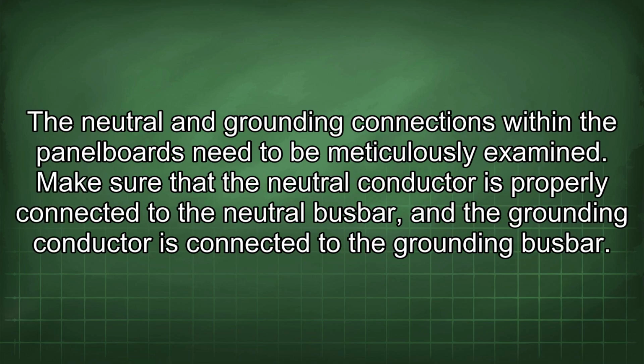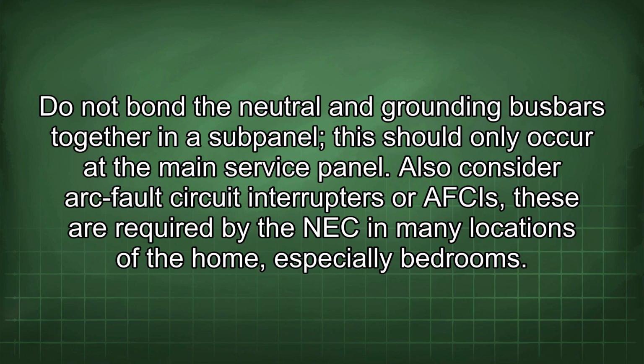The neutral and grounding connections within the panel boards need to be meticulously examined. Make sure that the neutral conductor is properly connected to the neutral busbar and the grounding conductor is connected to the grounding busbar. Do not bond the neutral and grounding busbars together in a sub-panel. This should only occur at the main service panel.